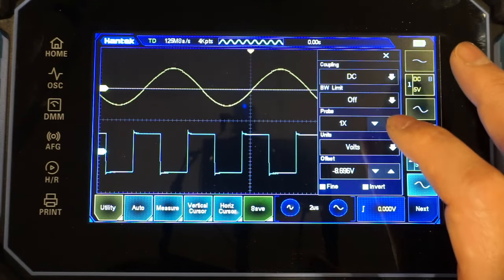And by the way, when you switch ranges, you can see that you are reminded where the leads need to go. Of course, that's just a visual indication, and it doesn't actually physically detect the placement of the leads. And for the current measurement, I'm putting the UNI-T UT61E Plus and the Hantek TD1204D in series. And currently, I'm outputting a roughly 100 milliamps current from the 6181C current source. And you can see the readings largely agree with each other.